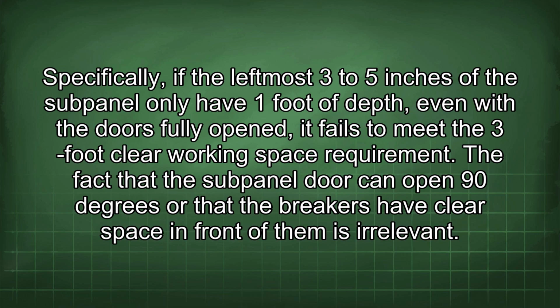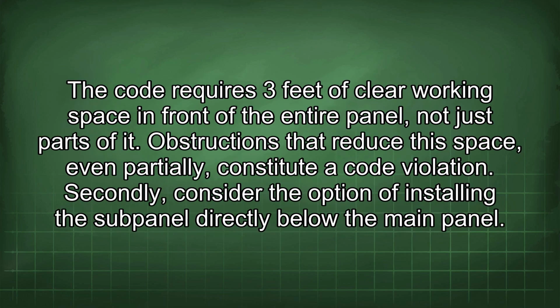Specifically, if the leftmost 3 to 5 inches of the subpanel only have 1 foot of depth, even with the doors fully opened, it fails to meet the 3-foot clear working space requirement. The fact that the subpanel door can open 90 degrees or that the breakers have clear space in front of them is irrelevant. The code requires 3 feet of clear working space in front of the entire panel, not just parts of it. Obstructions that reduce the space, even partially, constitute a code violation.